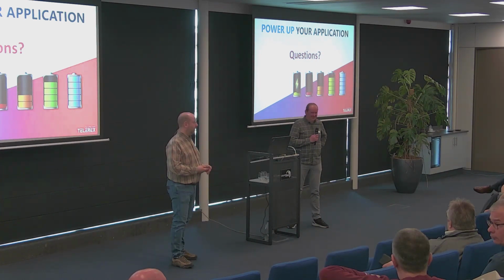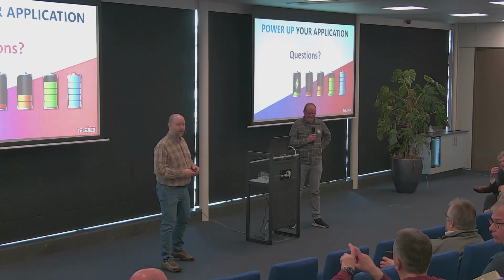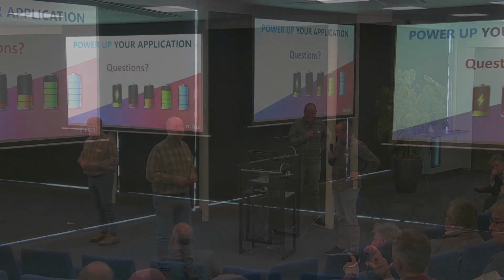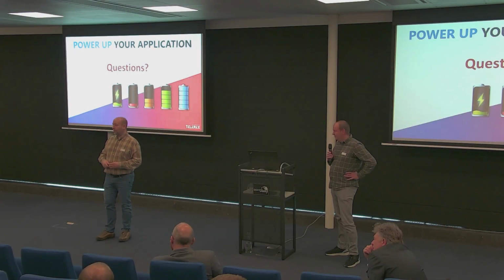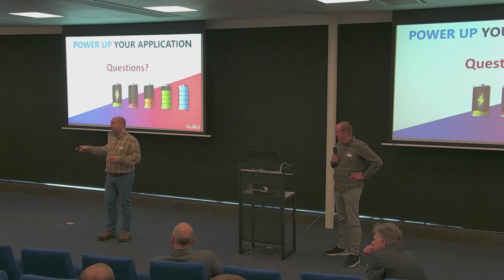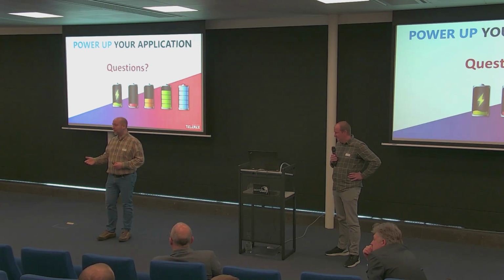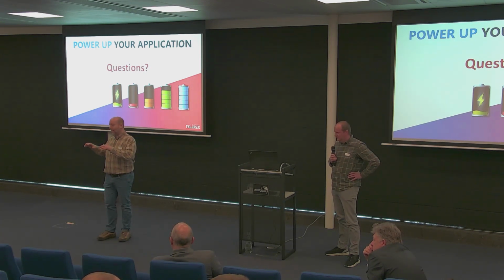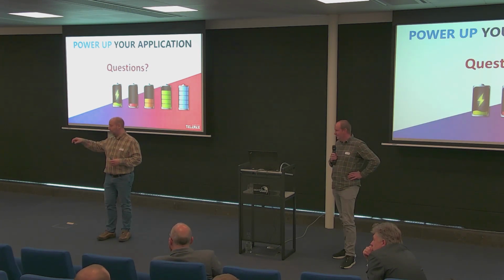Active balancing is only to the next battery cell. If you have a very unbalanced pack, well, in theory you won't get very unbalanced because you start balancing from the start, so you try to avoid an unbalanced pack. During these energy transitions, it's always a very small amount of energy that moves from one cell to another. The exact algorithm depends from chip to chip, but it's actually from one cell to the next, not from cell 1 to cell 10 or something - that's not done.